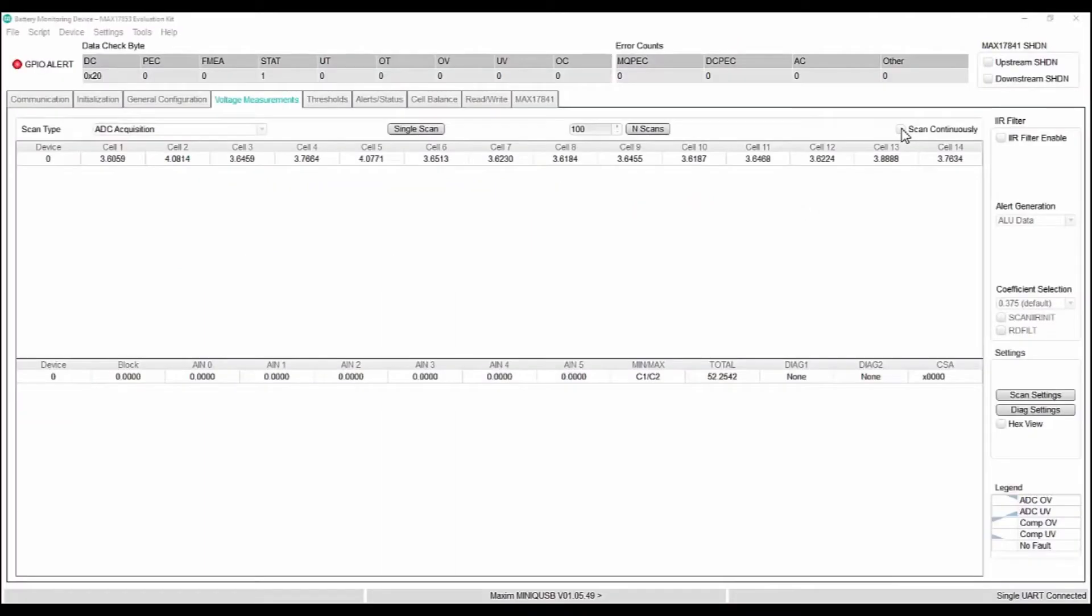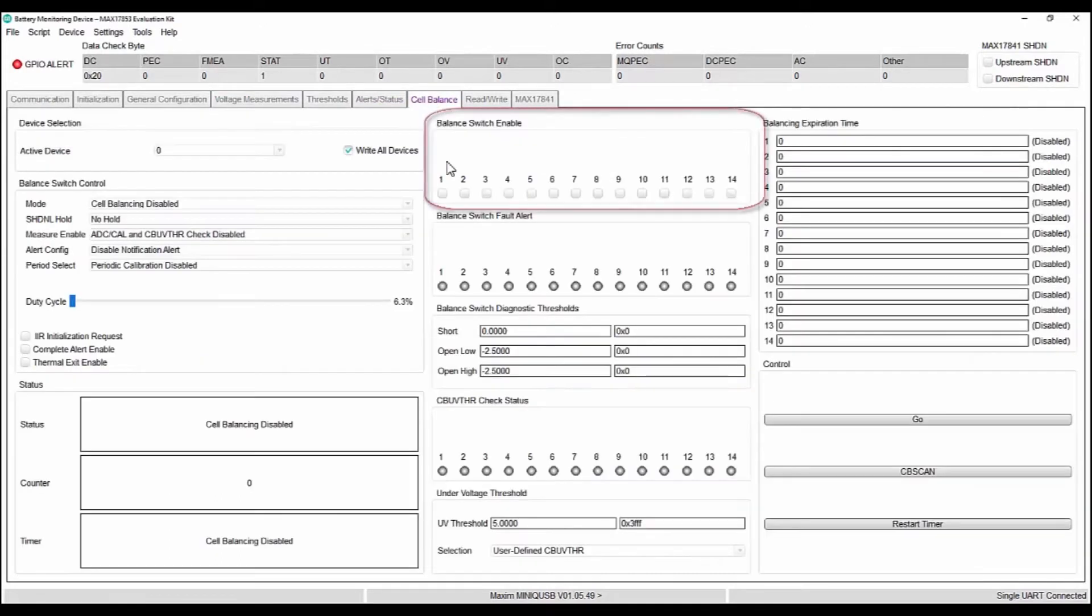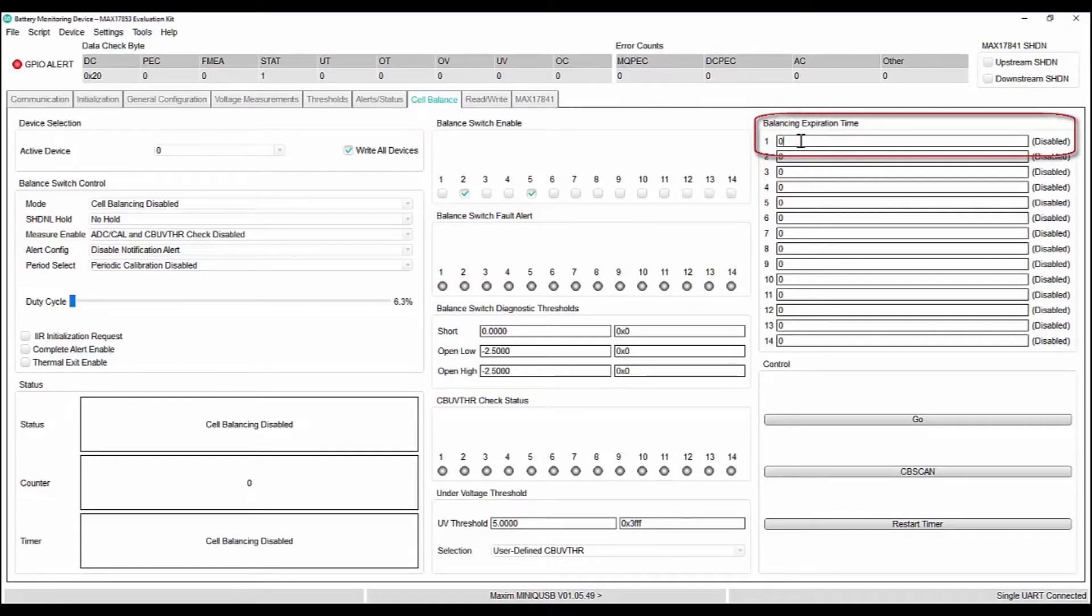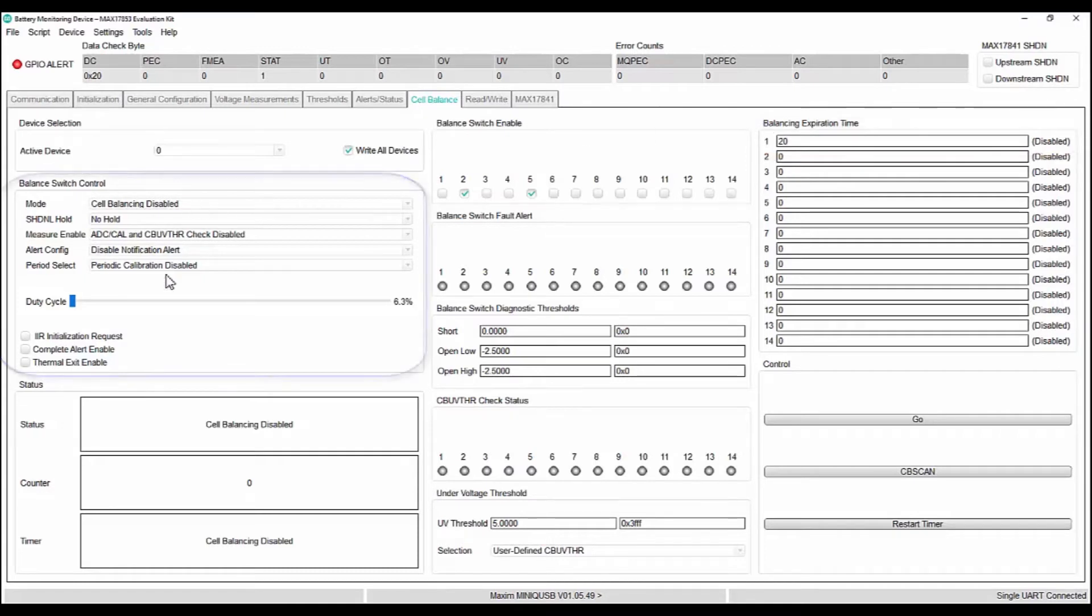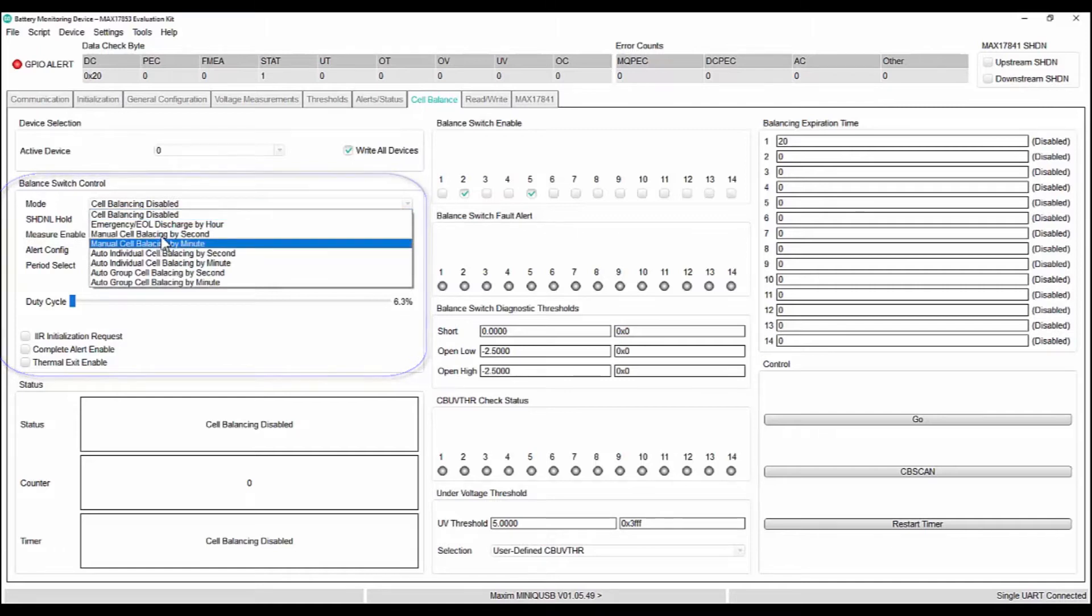Let us now do a manual cell balancing of cell 2 and 5. Select these cell switches, 2 and 5, in balance switch enabled and give a balance expiration time of say 20 seconds. And then come back to the drop down menu under balance switch control mode, select the manual cell balancing by second.